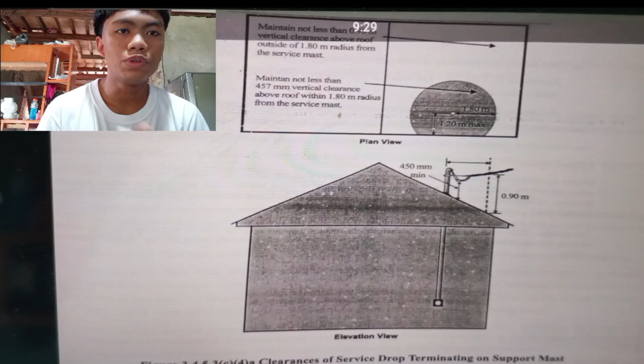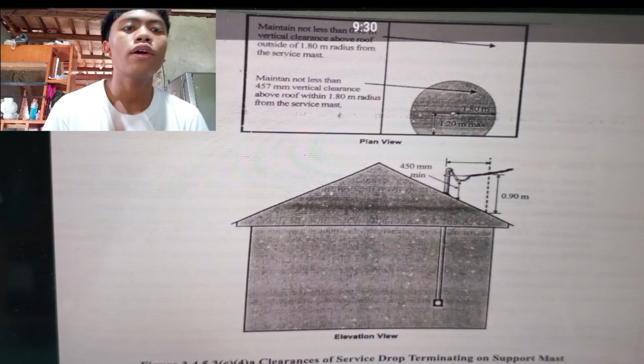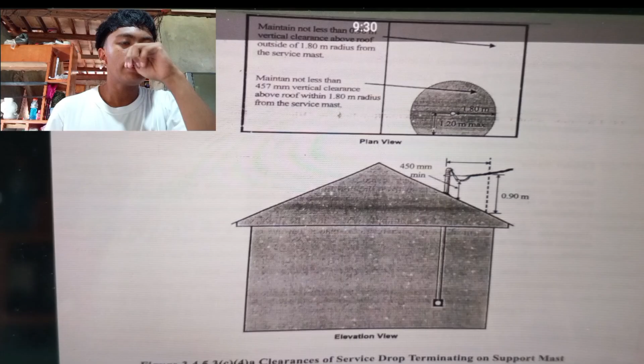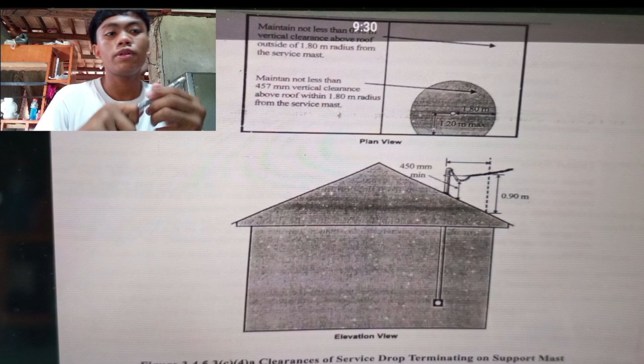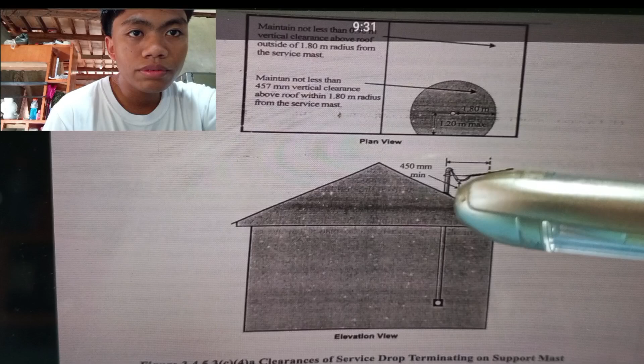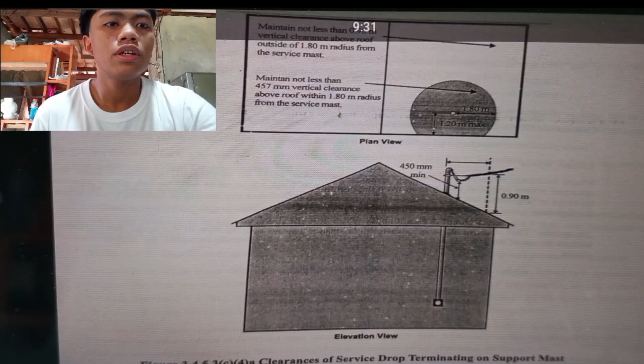And then maintain not less than 457 millimeter vertical clearance above the roof within a 1.80 meter radius from the service mast. As you can see here, I'm going to use this ball pen. This is the mast that the service drop can hold. This is the 0.90 meters from the roof vertically. So from the service mast we have a vertical clearance of 457 millimeter above the roof, within 1.80 meter.